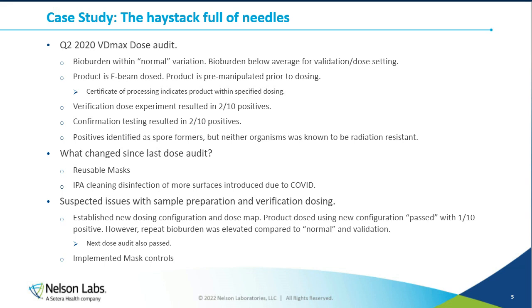Because the product is E-beam sterilized, there were also some changes in the background that we weren't entirely aware of, but the manufacturer suspected that there was an issue with either the sample preparation or the verification dosing itself. So as part of this, we came up with a new configuration for the product to establish a better verification dose so that it could receive a tighter dose range when verification dosing. We also improved our practices when it came to manipulating and packaging the product, adding additional layers to the product because since it was manipulated, we had a lot of sharp edges. So there was a feeling that really that was the true root cause.